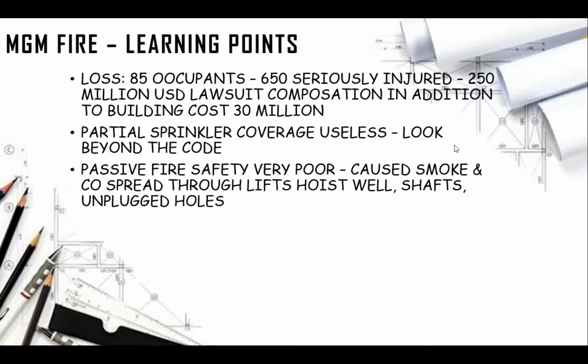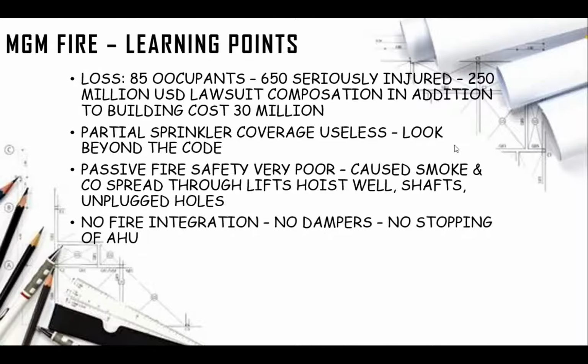This gap still exists in many buildings. In many modern buildings, passive safety is not highlighted or insisted upon, and is not provided, not maintained, and not tested. All these things happen with passive fire safety. And there was no fire integration, no dampers. It's very pathetic. The AHUs are there, but the AHU doesn't stop during the fire. See, normally when the alarm gets activated, the AHU must be stopped. The AHU and the alarm system must be integrated. This is called fire integration.